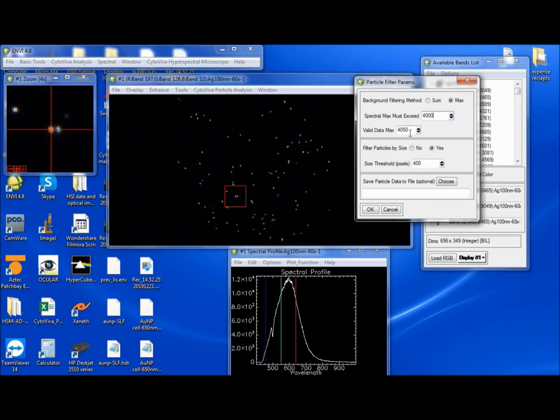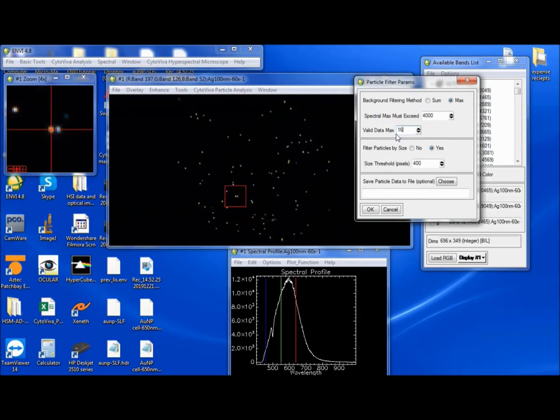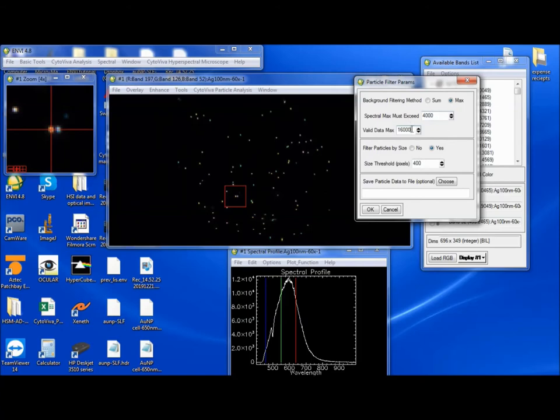And I believe we said we're going to put 4,000 as the minimum. So anything below that won't count. Maximum. So when this particle filter tool was made, we had a camera attached to our spectrographs that peaked at 4,050. It was a 12-bit camera. Now, in the last three or four years, we've sold cameras that are 14-bit, so this number actually will go to 16,300, but I usually just put 16,000 as the max. This is the dynamic range of the camera. It goes from 0 to about 16,300. But to be safe, I always put 16,000.